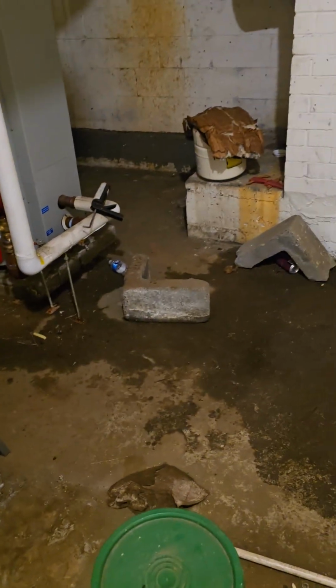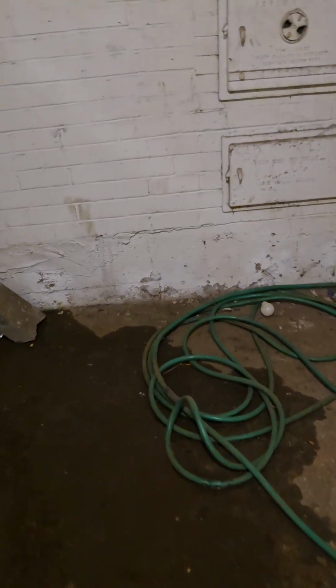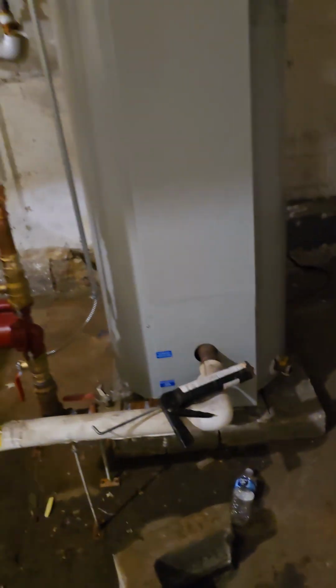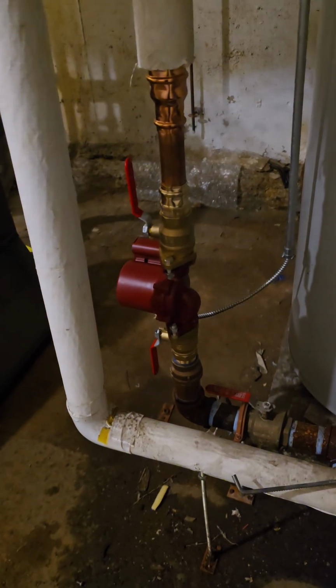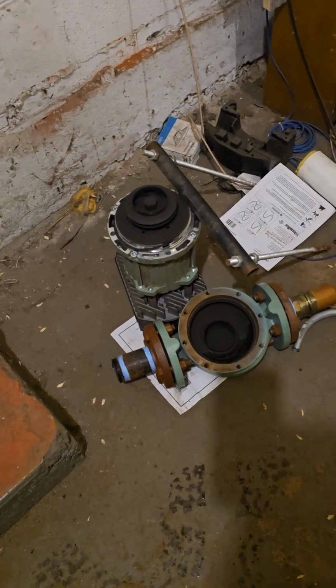Something I noticed, and this doesn't take much familiarity with this stuff: I have a little Grundfos 2699 installed, and this ridiculously large Taco Viridian was installed in its place. Since this is a turbo store, the tank is the actual boiler water and the coil inside is the heat exchanger, so there's no head loss.